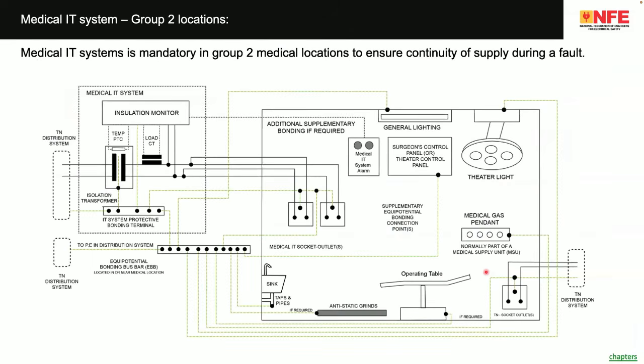Group 2 medical locations need additional safety measures such as the medical IT system. Here the concept is, in a group 2 medical location, the life of the patient is supported by electricity, and in case of disconnection of supply during a fault, the patient's life is endangered. In order to avoid that, there is an additional supply system, as you can see here, the medical IT system. Please note, it is not a UPS with an isolation transformer. It is not an isolation transformer alone of maybe 25-30 kVA. No, a medical IT system has certain specific requirements. A medical IT system is a special panel board with an isolation transformer, with an insulation monitoring device, with leakage current monitoring devices and multiple safety measures specifically for certain equipment which is used in the operation theater, for example.